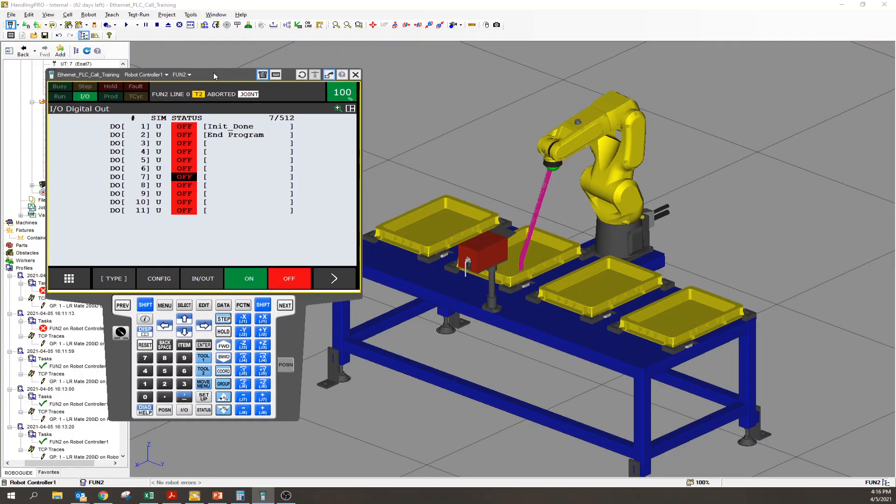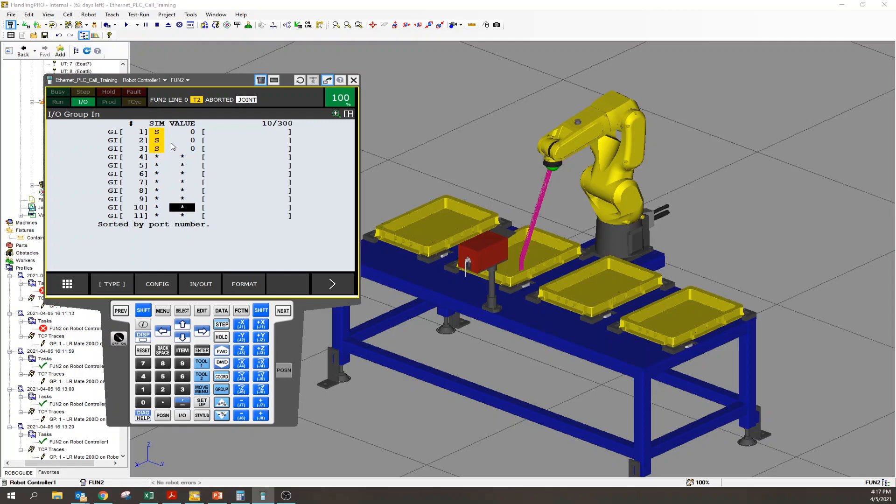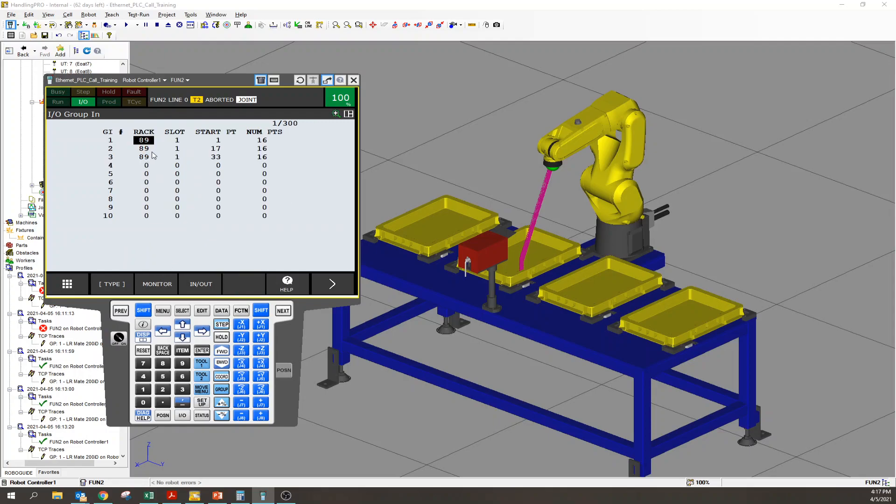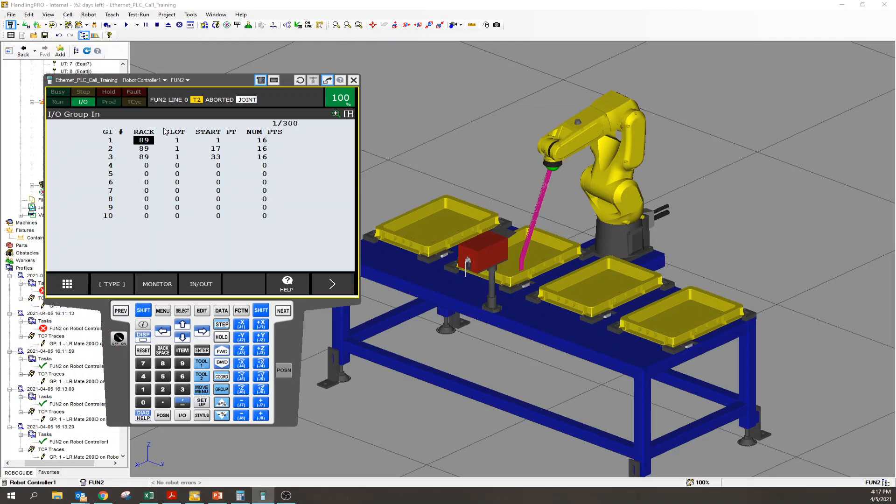Alright, this is all tips and tricks. So let's set up some group I/O. I already set up three of them, I'm going to show you what I've done. I'm assuming that this robot is talking to an Allen Bradley PLC over ethernet as a slave or adapter. So all of my group inputs are rack 89, slot one - that just means I'm talking over ethernet. That's my ethernet comms. The next thing you'll see if I jump over here, it says number of points. This is how many bits do I want to lump together.